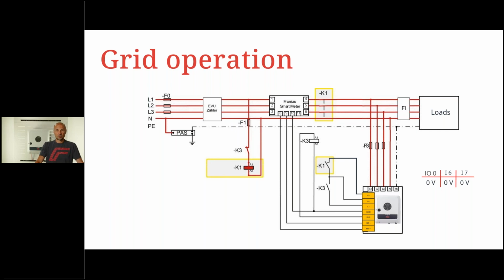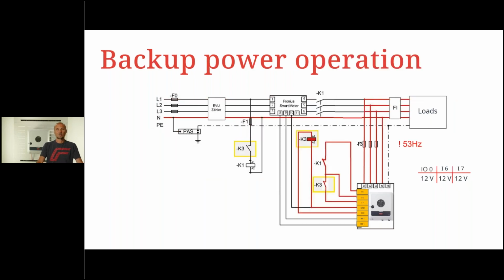So as soon as there's a grid outage, the contactor will open the 3 phases in this case, and then the inverter will get feedback from K1 normally closed contact on input 6, then give the K3 the signal to start, so that our small relay will then be supplied, close also contact input 7, and interrupt the line from K1 from the coil.